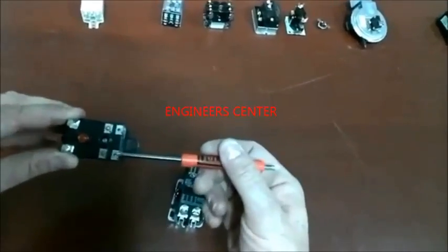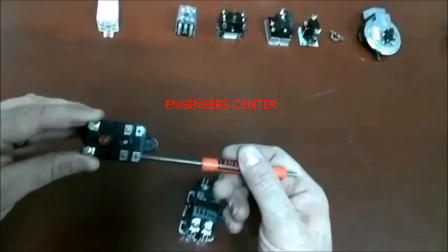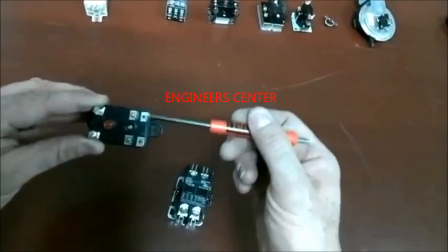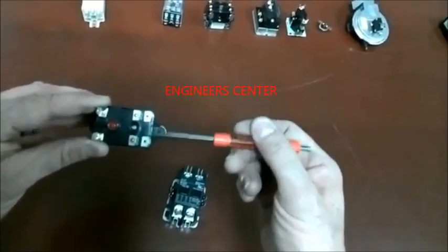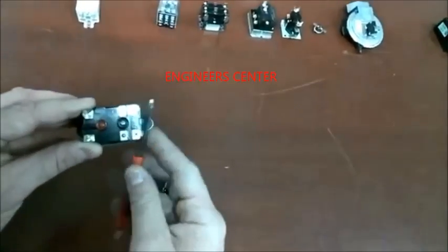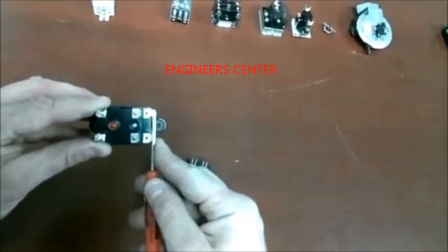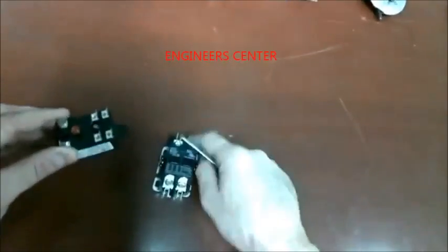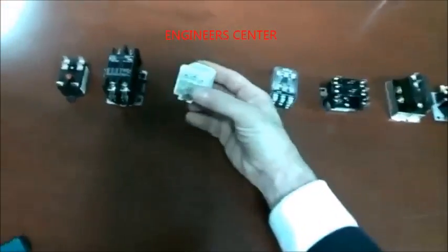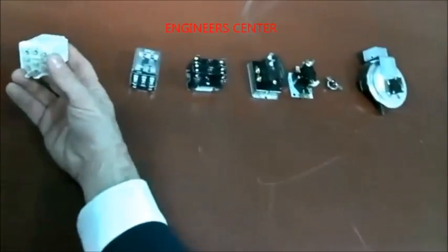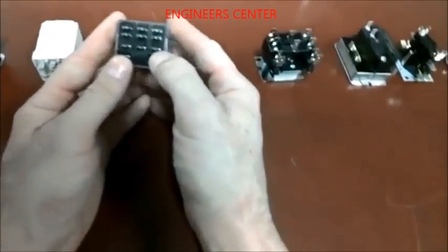and you had power here, it's normally open, and so this terminal and this terminal are normally open, meaning they're not connected with continuity. But if you give this 24 volts, they become closed, and so they connect, sending power to the other side, just like this. And so this is also a relay, just the same thing. It just looks a little different. They like to confuse you, but originally this is just another relay.